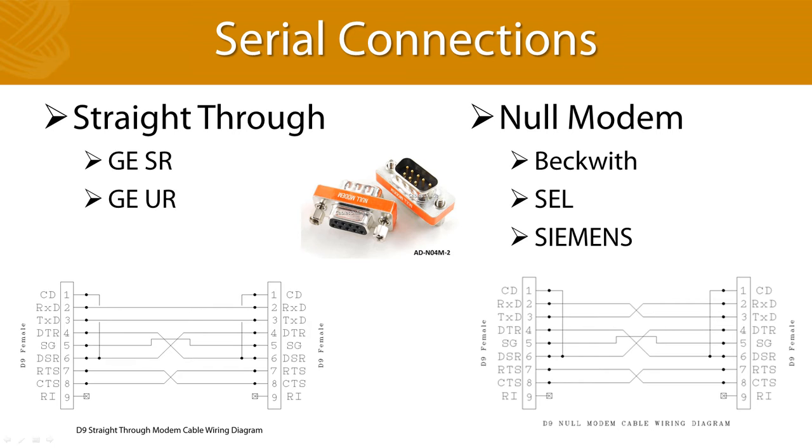For those of you who might have bought a special cable or Bluetooth adapter from SEL, you can use those cables on a GE relay by simply changing the DTE-DCE switch to the other position. That switch is the null modem connection to a straight-through that you can use whenever you want to. Just remember to put the switch back when you need a null modem again.